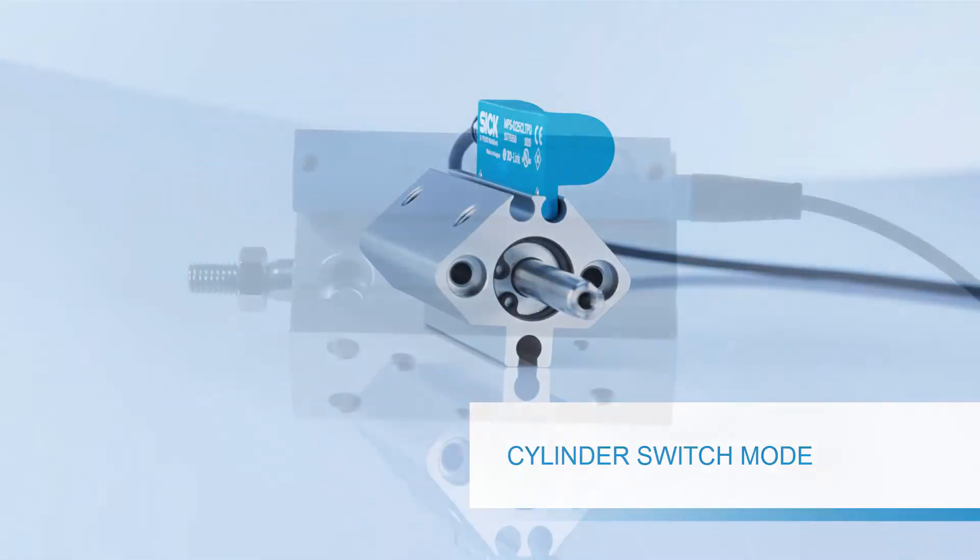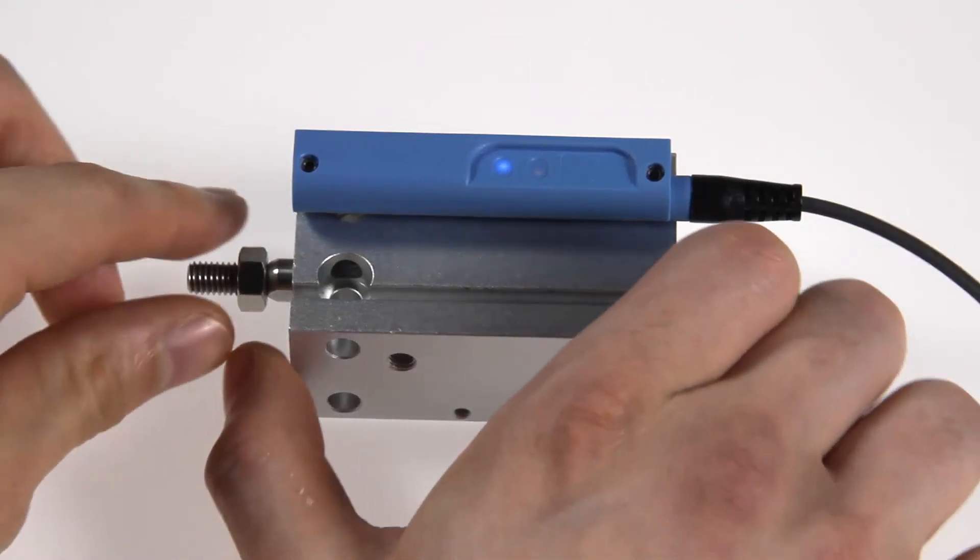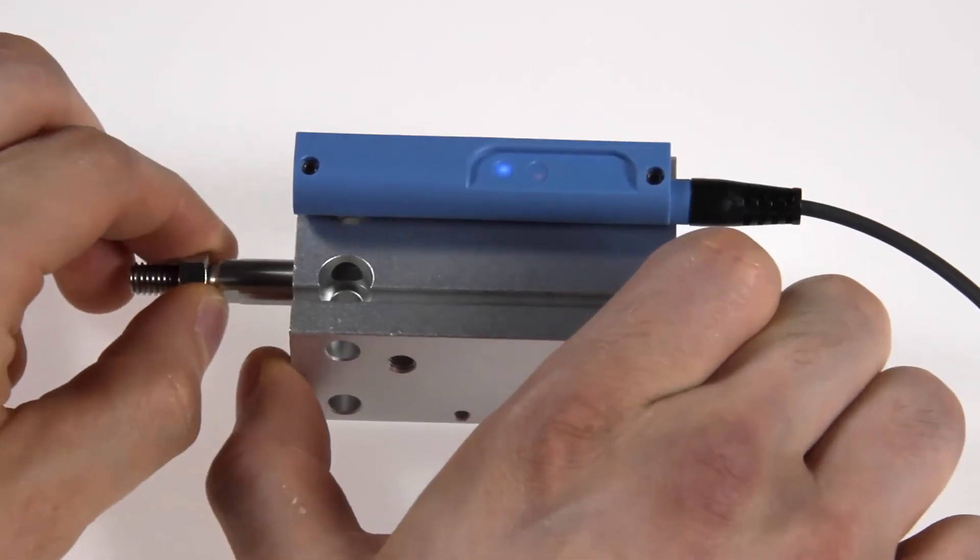Cylinder switch mode. This mode defines a switching point with a hysteresis around the switching point. This mode is similar to what we are used to from standard cylinder sensors. To set the switch point, push the piston in the desired position.